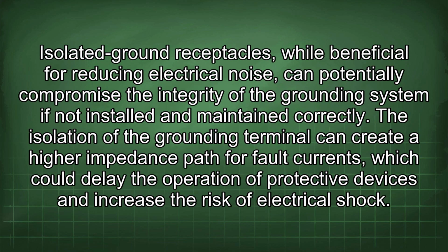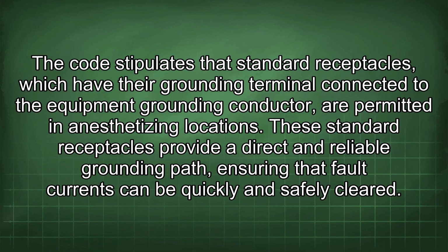Isolated ground receptacles, while beneficial for reducing electrical noise, can potentially compromise the integrity of the grounding system if not installed and maintained correctly. The isolation of the grounding terminal can create a higher impedance path for fault currents, which could delay the operation of protective devices and increase the risk of electrical shock. The code stipulates that standard receptacles, which have their grounding terminal connected to the equipment grounding conductor, are permitted in anesthetizing locations. These standard receptacles provide a direct and reliable grounding path, ensuring that fault currents can be quickly and safely cleared.